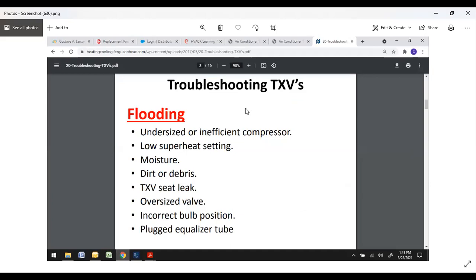So, troubleshooting TXVs. TXVs seem to be the biggest pain. They're not that difficult. A lot of times it's not their fault. You get dirt, debris, junk in there, and it fouls them up. So if you're flooding your evaporator, it could be due to an undersized or inefficient compressor. Low superheat setting, if you have an adjustable TXV, which really wouldn't come into play with most residential TXVs, they're already preset. You could have moisture. You could have dirt or debris that's causing the valve to stick open. TXV seat leak. You could have an oversized valve. Incorrect bulb position, or a plugged up equalizer tube.